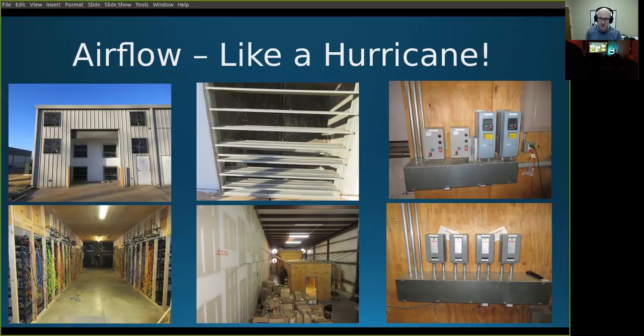You can see in the bottom middle picture, it's a deep, long industrial space. Most spaces aren't deep and long like that. They're shorter and wider. So in that case, you'd use multiple hot and cold aisles, but you'd still want to direct the air where you provide a cold aisle section and a hot aisle section, and you exhaust out the hot aisle.